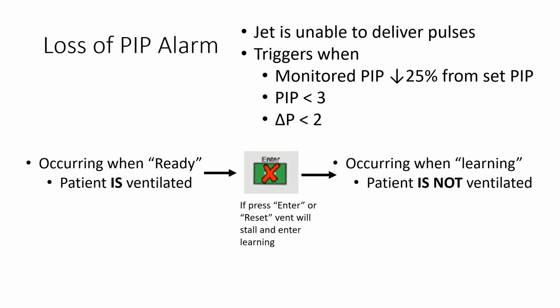Common causes of this alarm are leaks or disconnections within the ventilator circuit, malfunction of the pinch valve in the patient box, condensation in the tubing, suctioning without putting the jet in the standby mode, or the patient spontaneously breathing, crying, coughing, hiccuping, or needing suctioned.